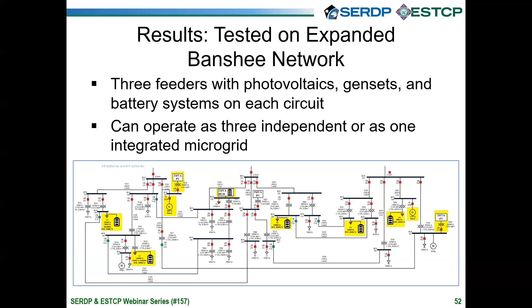We made some extensions to this, adding a couple of PVs and generators to make it a little more realistic. This is the example we use. The good thing is that there are OPAL-RT high fidelity models for this, and they also have simulated low-level controllers that we interact with using standard Modbus protocols. So if an inverter is available on the model, we can talk to it using our Modbus implementation and directly perform the control actions.